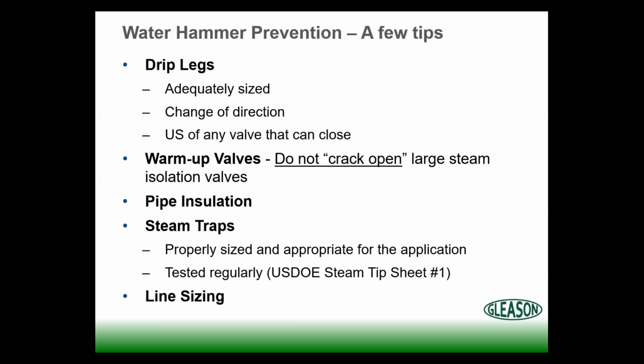We don't want to crack open large valves. We want to use warm-up valves. And a warm-up valve is simply a small bore valve, some people may call it a bypass, around any steam isolation valve 3 inches and greater, so we can warm that system up slowly instead of trying to crack open the large valves. So just simply a rule of thumb there is 1 minute per PSI as a rule of thumb.